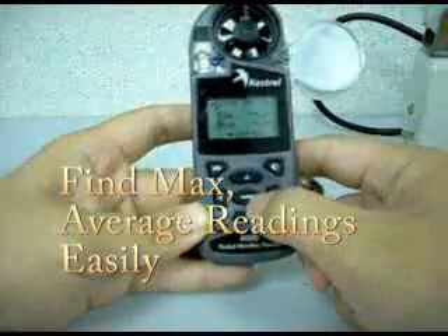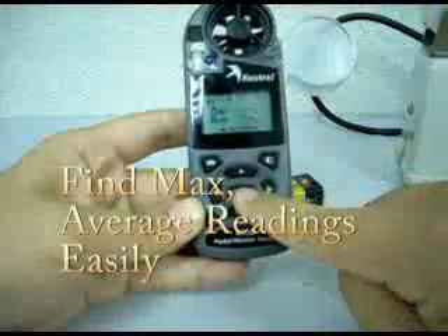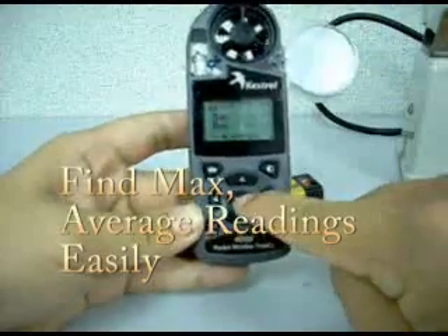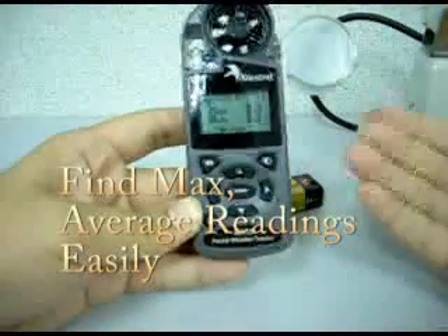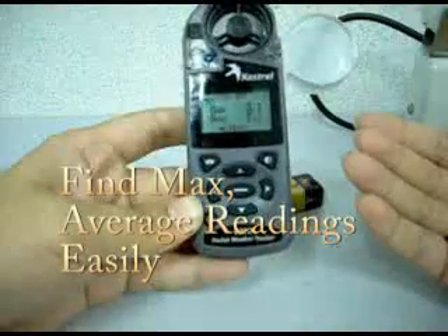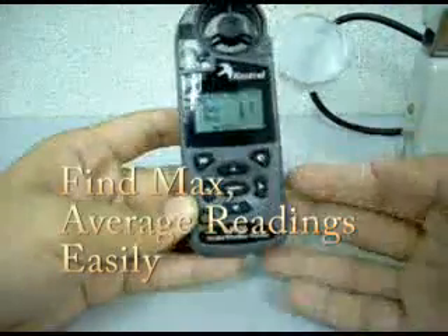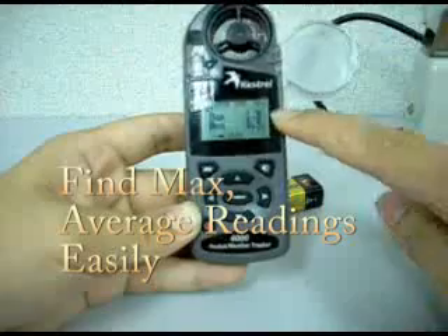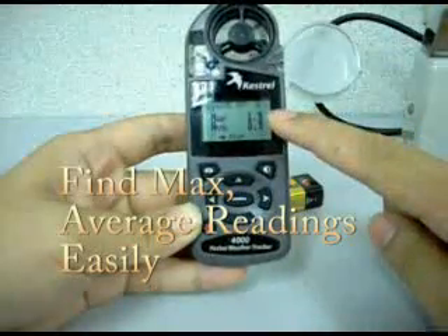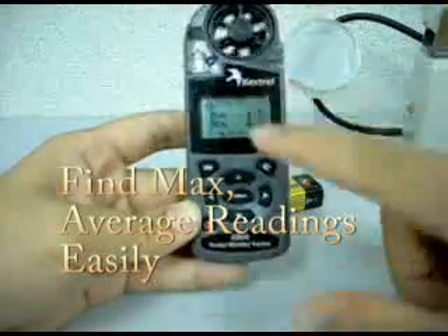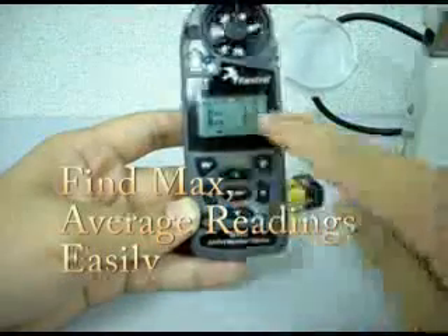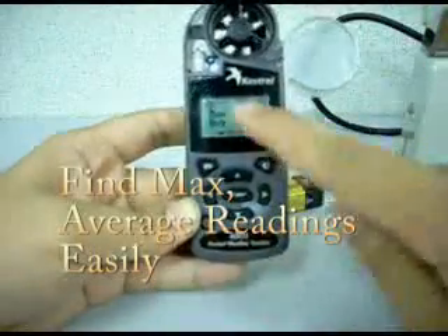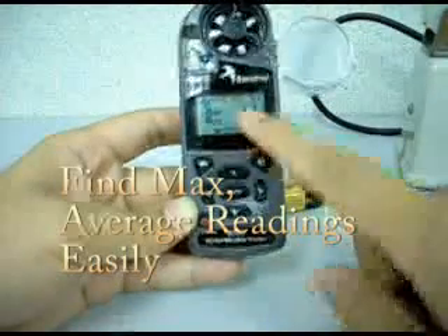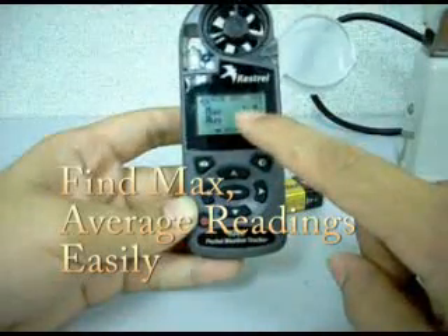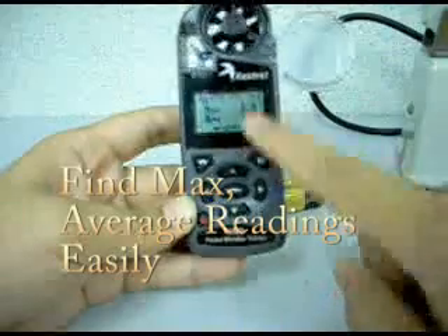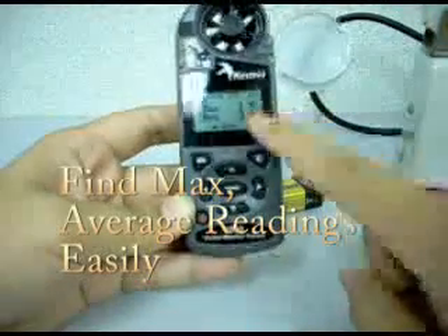To start finding the maximum value and also the average value, you press the middle button here. This button, press. Okay, you start taking the reading. For example, I blow. The first screen is showing you the maximum reading you've got within this period, from the time you press this start button until now. The second reading is the average. Average is every wind speed you've taken divided by the time taken in terms of seconds.